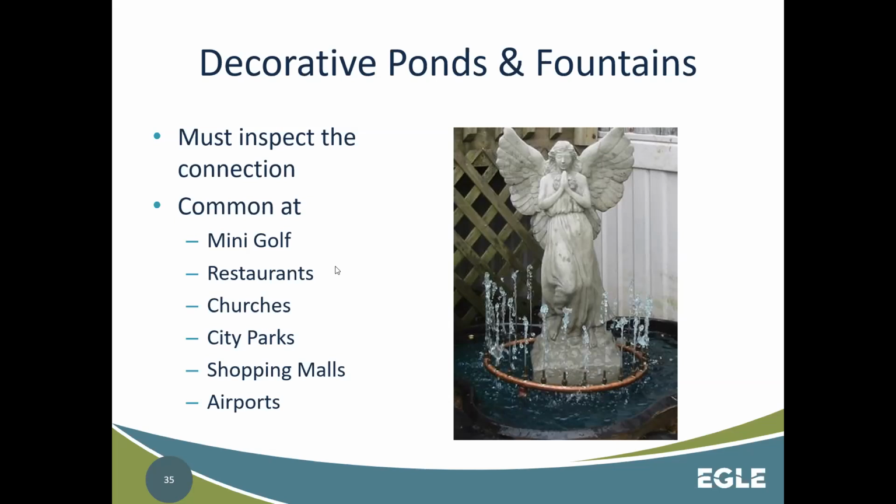The next morning when they came back to the fountain, it was completely empty. And basically what happened is while that fountain had been left to fill, the fire department went out to do some exercises and was using their pumper truck, and it actually caused a localized depressurization and pulled all of the water out of that fountain back into the system.